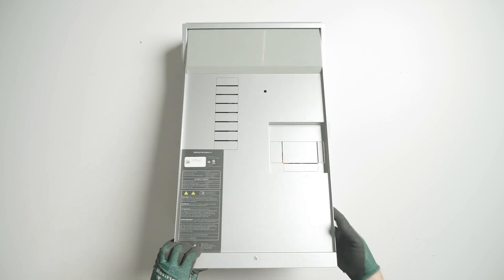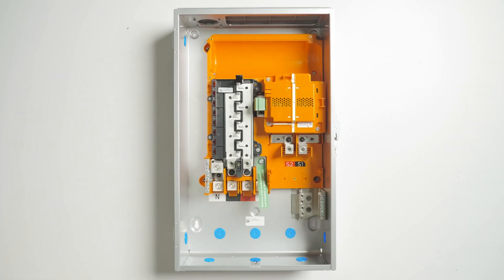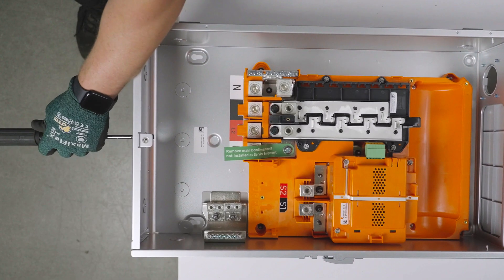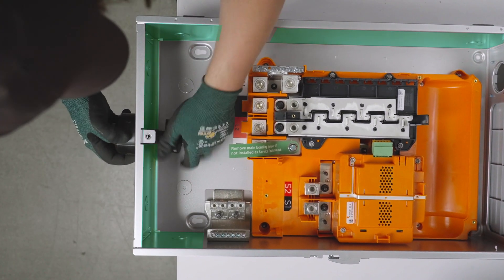Before mounting the enclosure, remove the dead front and make the required conduit entrance knockouts. These knockouts can be expanded to accommodate larger conduit, or new knockouts can be made in this area.